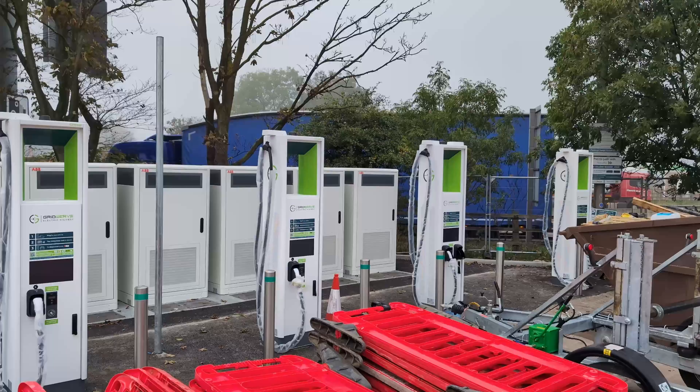After this, the situation can get very murky indeed. How much power is taken from the substation during installation versus how much power all of the chargers together — each delivering the maximum of 350 kilowatts in this case — can use? Different installations will make different decisions. If we go back to houses: houses are rated generally in the UK at 230 volts and 100 amps. Some houses have 60 amp limits but they're fairly few and far between. Therefore each house is quite capable of 230 times 100, or 23 kilowatts.